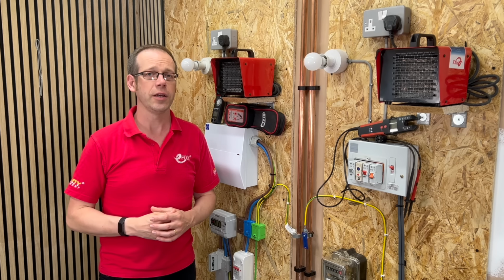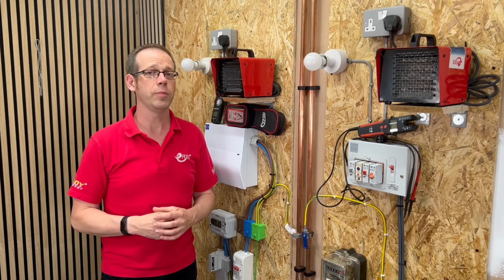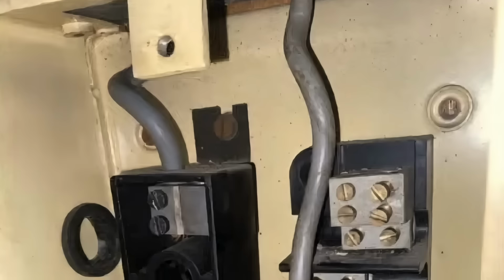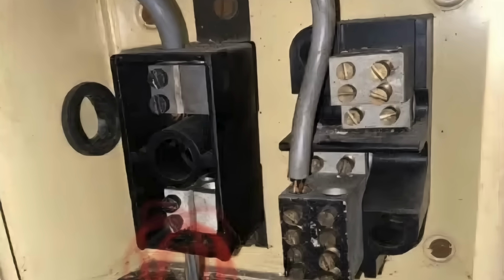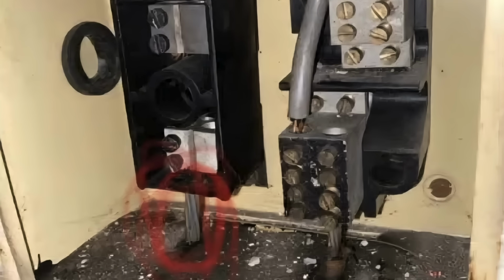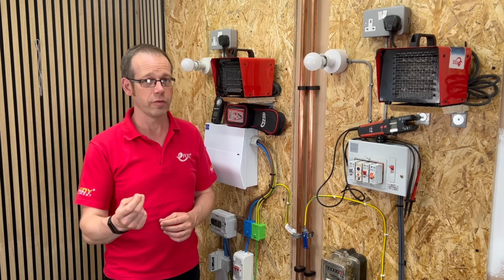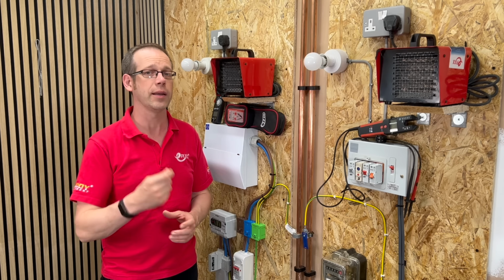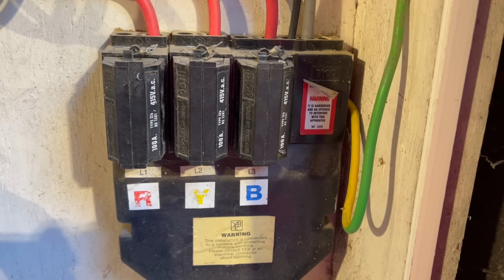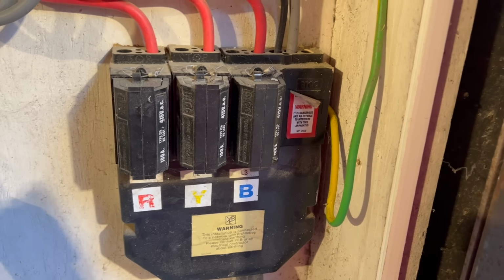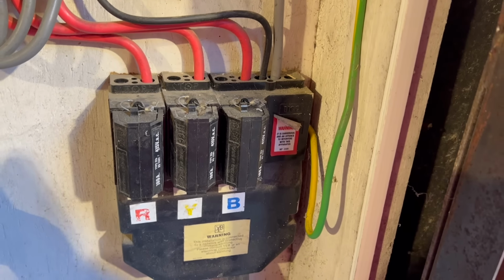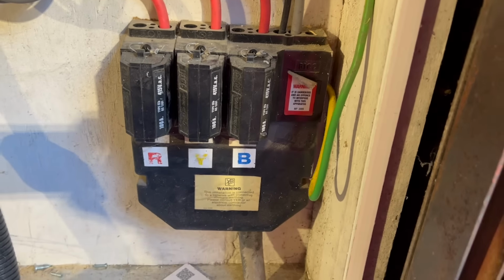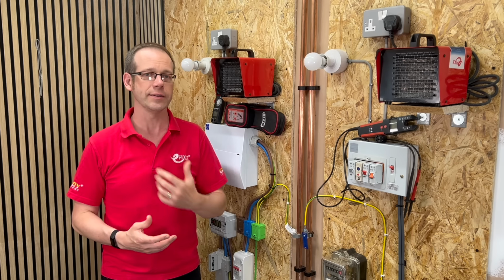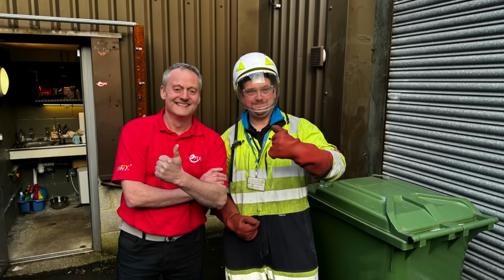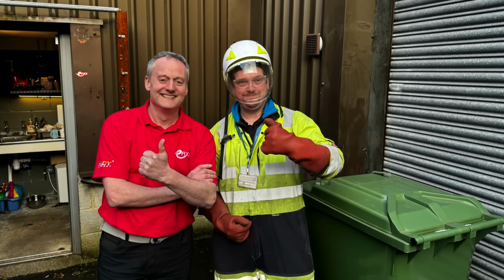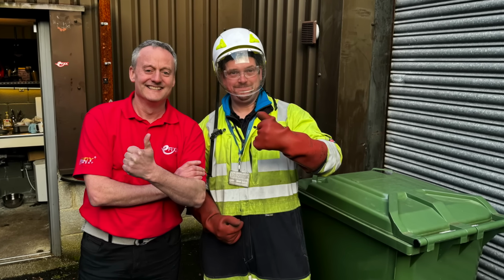Although typically sealed and considered not to be tampered with, these components can present serious hazards when they become damaged or degraded over time. For electricians, understanding these dangers and following appropriate precautions is critical for personal safety and compliance with regulations. If you're working near supply equipment, remember the cable and service head may be over 100 years old and might not have been inspected for decades. That's why it's essential to follow industry safety guidance. Always wear insulated gloves, use a full face visor, and assess the condition of the equipment before touching anything.